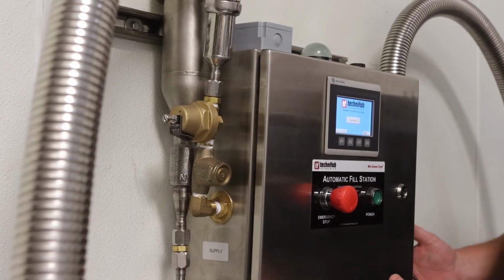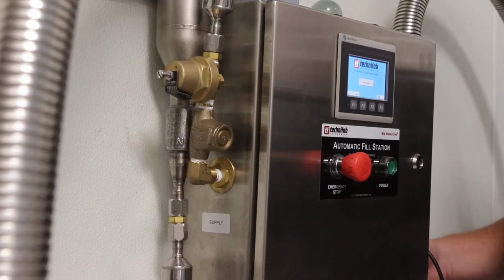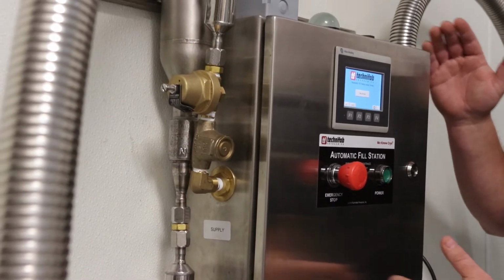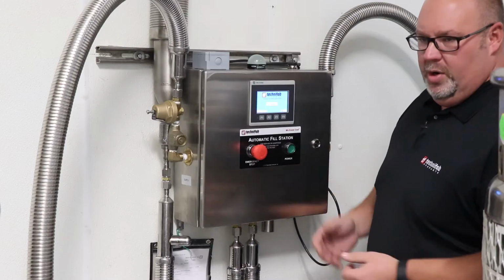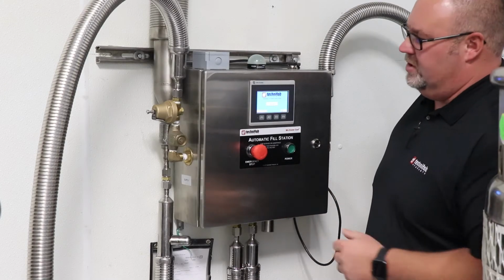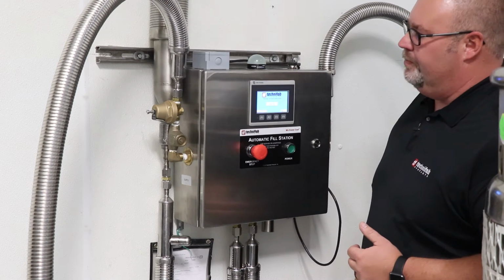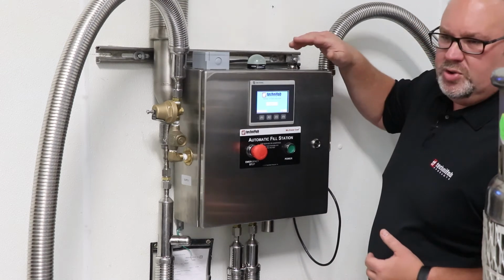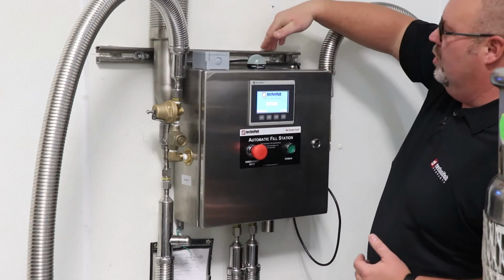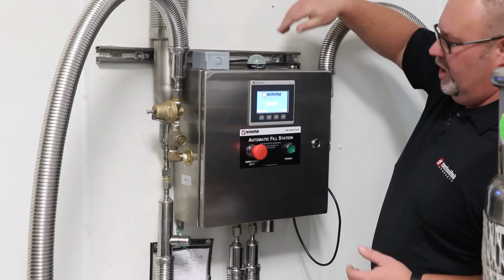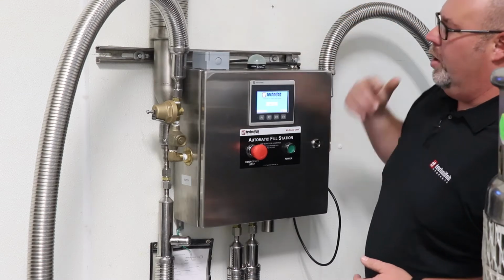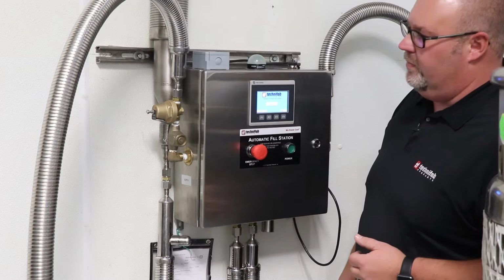This is what your automatic fill station will look like mounted on the wall. It needs to be mounted in a vertical position. It will not work in the horizontal position due to the sensors on the inside. It comes with bracketry. You can also use your own bracketry to mount. We used unistrut channel bracket and then mounted accordingly. The pattern on the back can be drilled in from there.